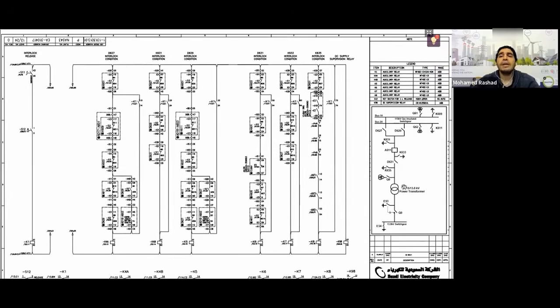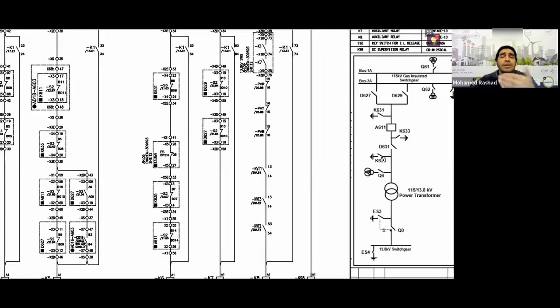Now, someone might ask, what if, Engineer Rashad, I didn't have a transformer here, what should I do? Well, if you have a space here instead of the transformer and you want to close the ground, it's very dangerous if you close the ground and the line is energized, right? How do I know if the line is energized? By looking at the voltage readings, but I can't be sure just by looking at the voltage readings. So what should you do?